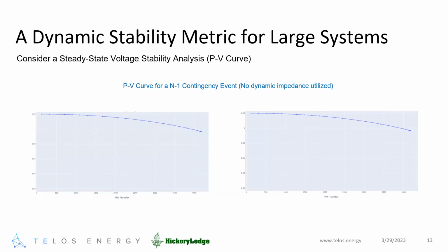We understand that as we load up the transmission system, as we transfer more power across it, voltage tends to decrease, and it ends up at a point where voltage collapses and it's no longer able to support. These two curves are identical, and they consider what we would do today, where those resources have a terminal voltage that is an ideal source, perfectly controlled in a steady state analysis, and you get a curve like that.